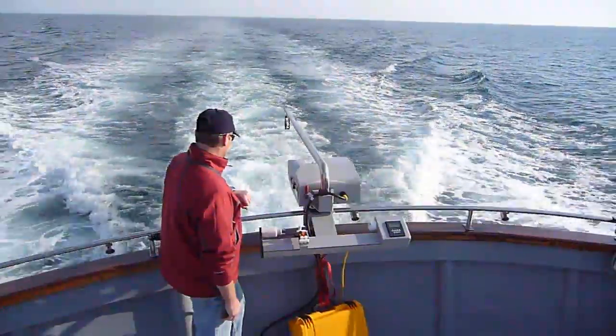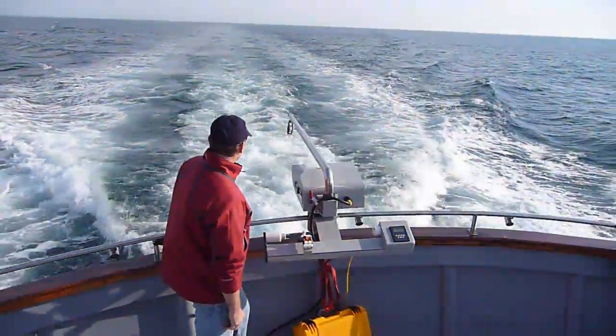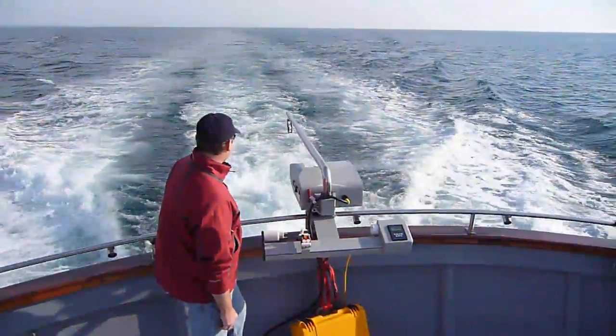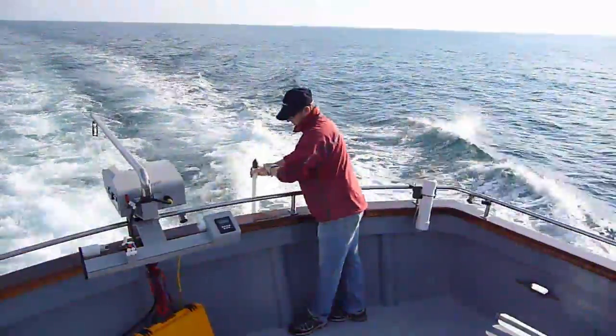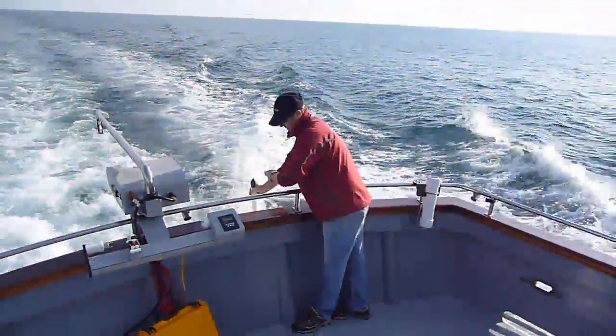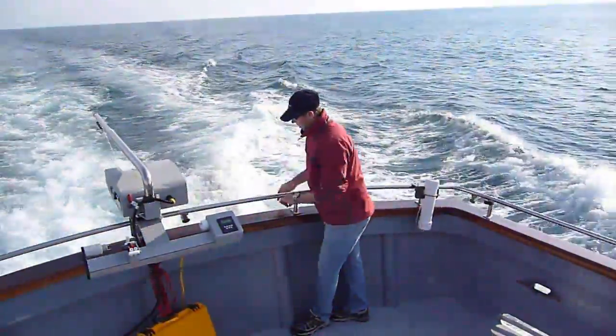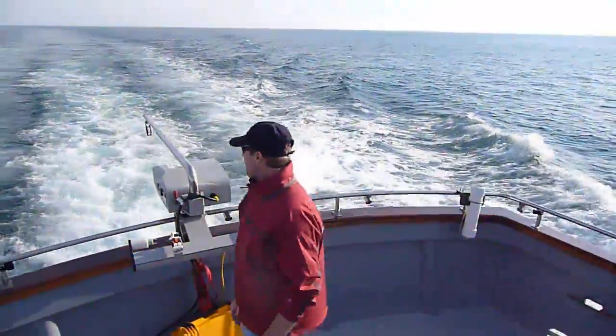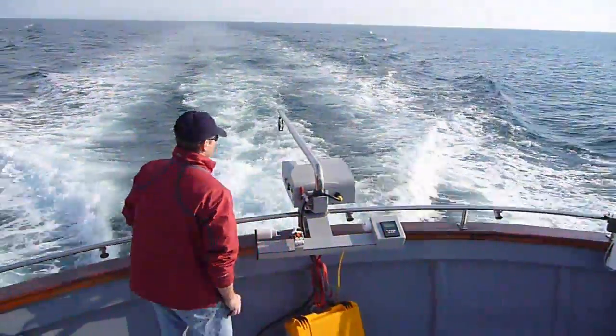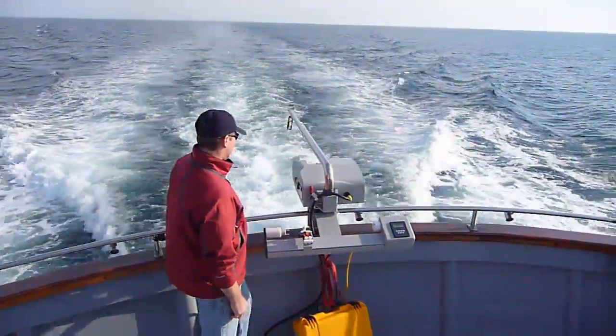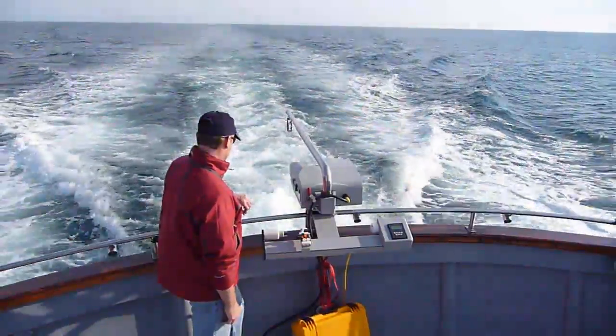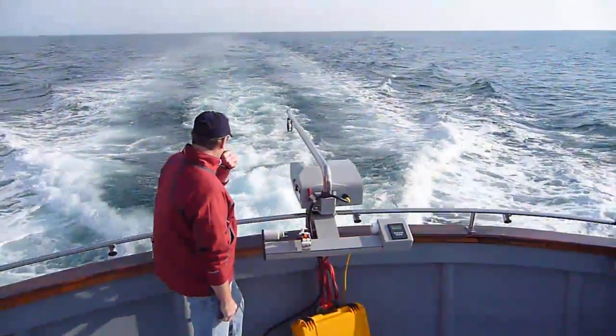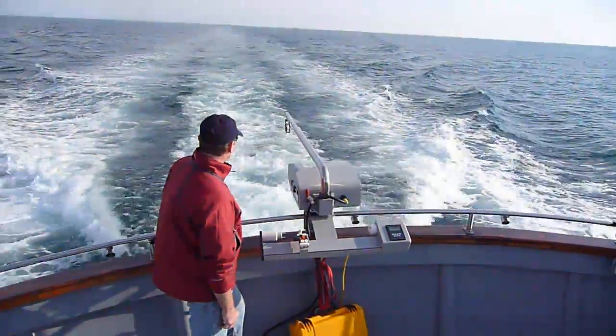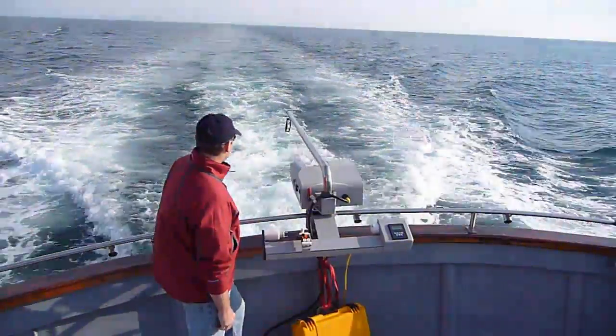So we'll take another look at that drop. And this time, have a look at the line as it comes off the winch. You'll see there really isn't very much tension on it. All the winch is doing is paying out line to account for the motion of the ship. Remember, as the probe drops, the line is paid out from the tail spool, so the probe isn't pulling any line off the winch.